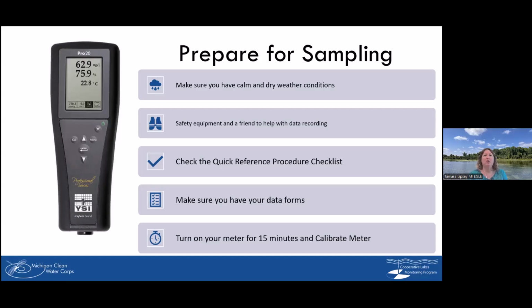Make sure you check your quick reference procedure checklist that's in your kit. Make sure you have your data forms, which we also provide. And then make sure you turn on your meter for 5 to 10 minutes, or 15 minutes if you have a 550A. It needs to warm up and the settings need to settle before you try to calibrate, or you won't be successful in your calibration.